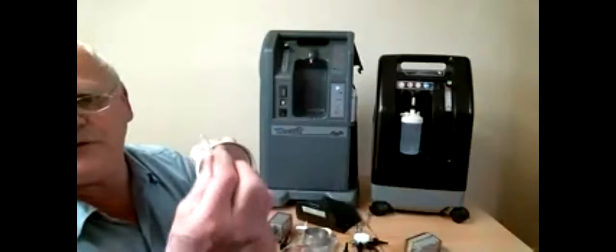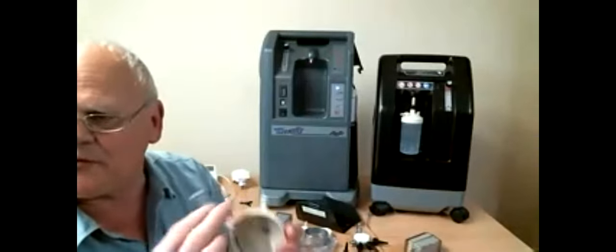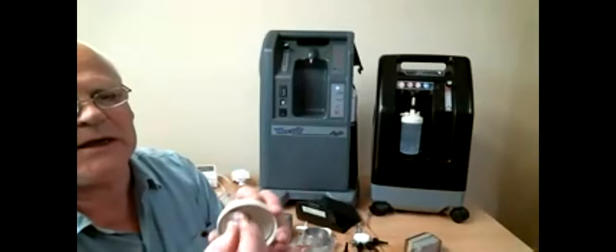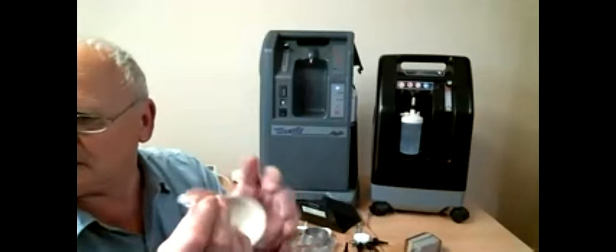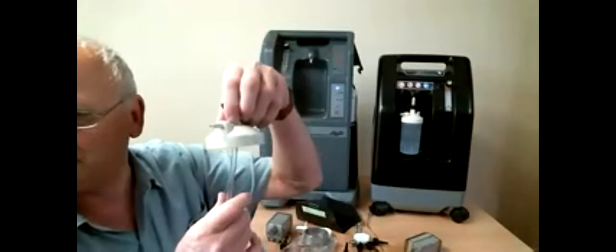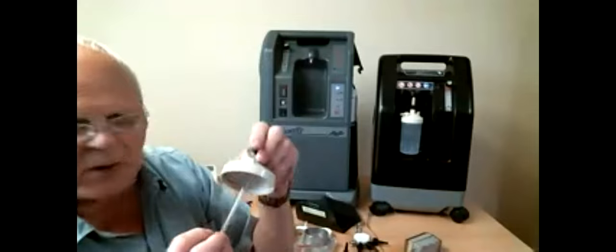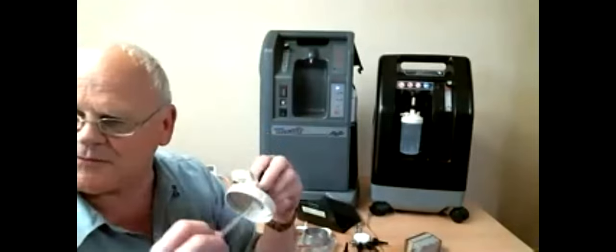Internally, they have a diffuser in the bottom end here. And quite often I get people say to me, the output from the concentrator is much lower than it should be. And it's often nothing to do with the machine. It's this end here, the little diffuser on the end of the tube in the humidifier bottle that gets blocked and crusty and then stops the flow through it.